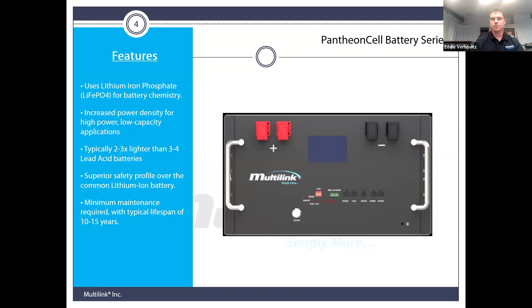Because of this chemistry, we have a higher depth of discharge compared to lead acid or AGM style batteries. This results in greater runtime and efficiency, as well as longer battery backup runtime.